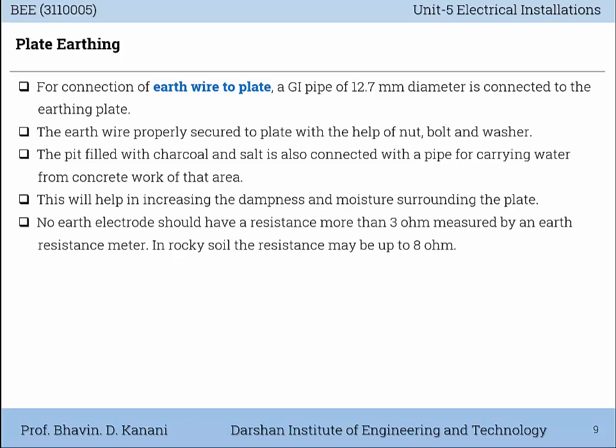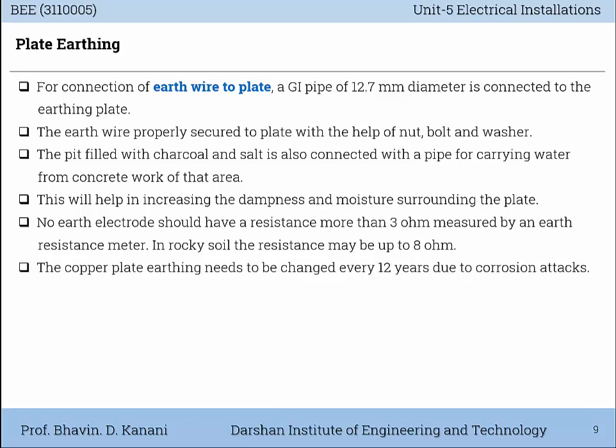No earth electrode should have a resistance of more than 3 ohm, measured by an earth resistance meter. In rocky soil, the resistance may be up to 8 ohm. The copper plate earthing needs to be changed every 12 years due to corrosion attacks.